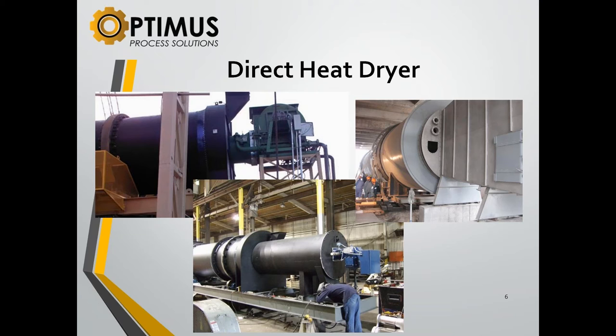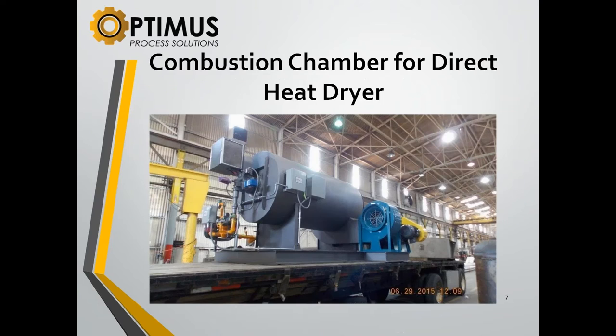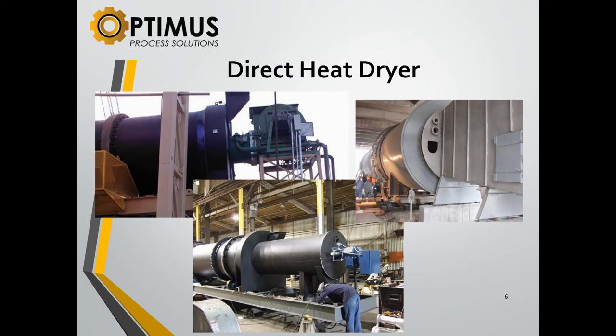The second group of dryers that we're showing right now is a direct heat type where we're bringing hot gases into the dryer. We're rotating and tumbling materials by lifting flights, and we allow that air to impart its heat load into the product, where it heats and volatilizes the water, and then the water leaves and the dry product comes out the end of the dryer.